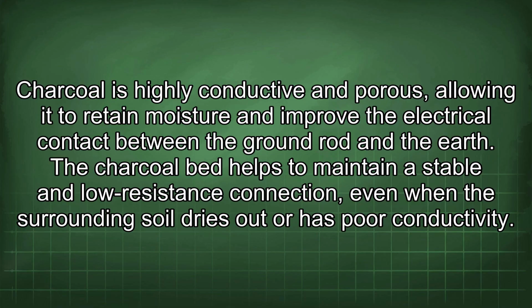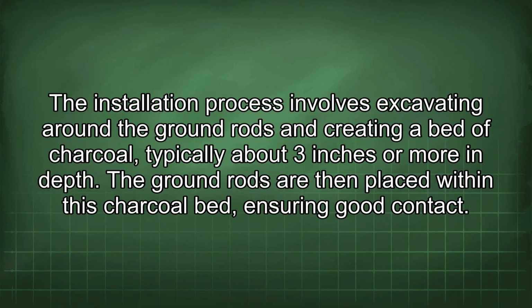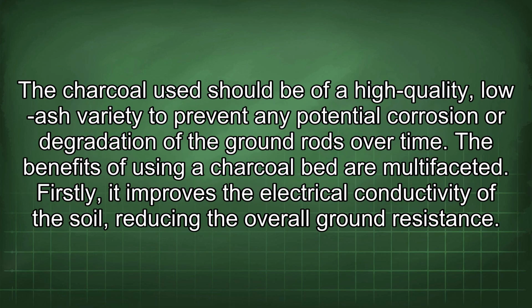The charcoal bed helps to maintain a stable and low resistance connection, even when the surrounding soil dries out or has poor conductivity. The installation process involves excavating around the ground rods and creating a bed of charcoal, typically about 3 inches or more in depth. The ground rods are then placed within this charcoal bed, ensuring good contact. The charcoal used should be of a high quality, low ash variety to prevent any potential corrosion or degradation of the ground rods over time.